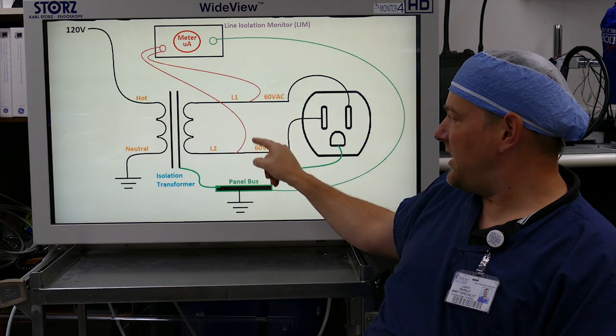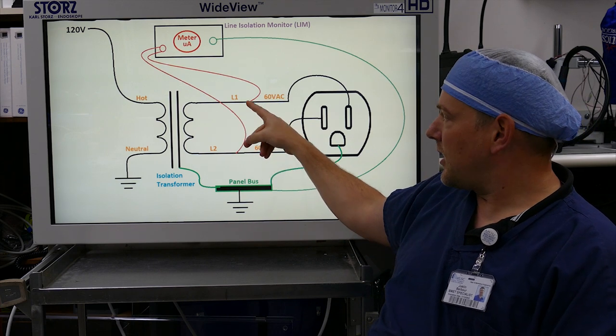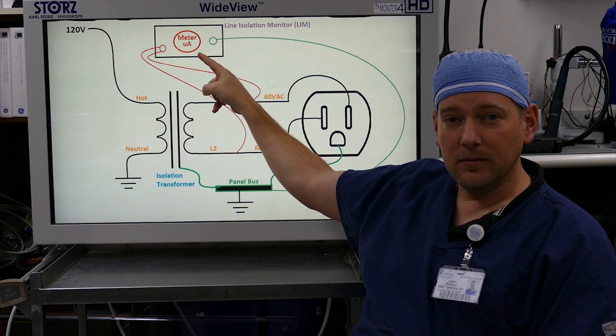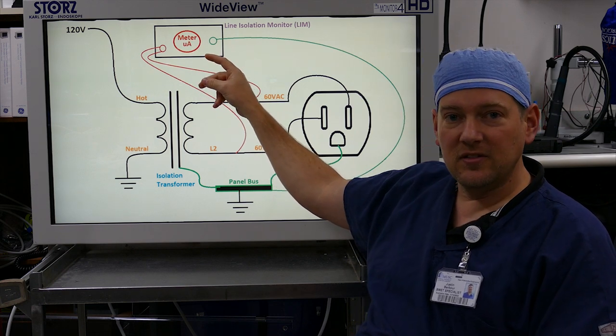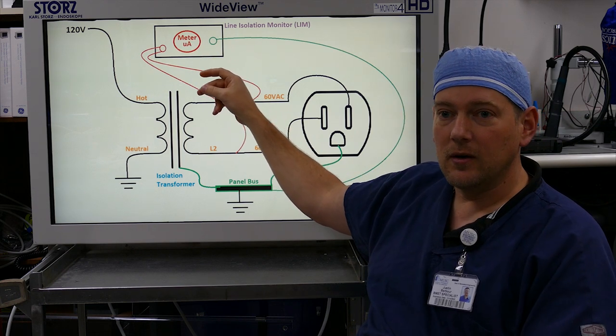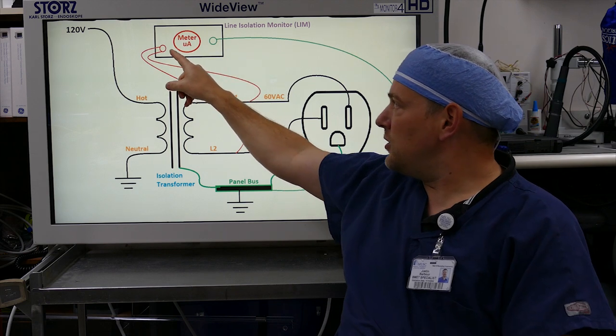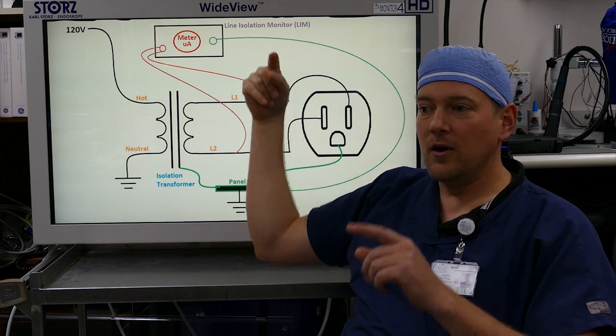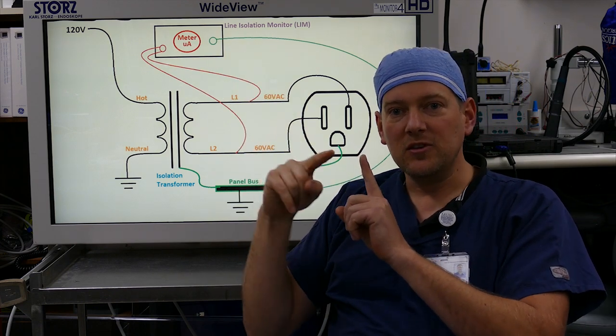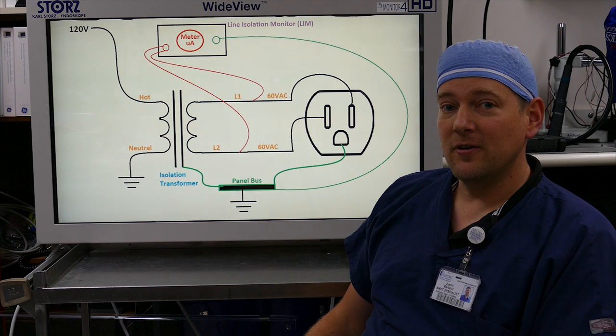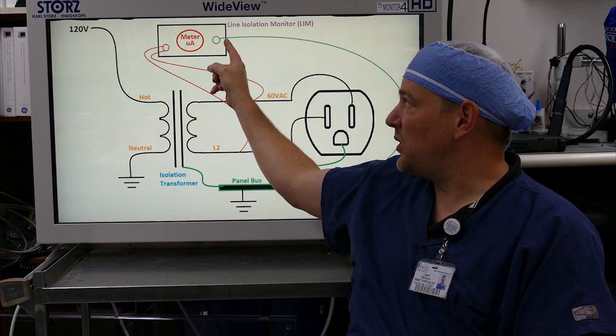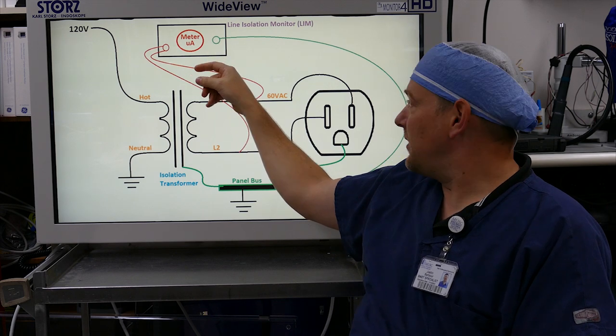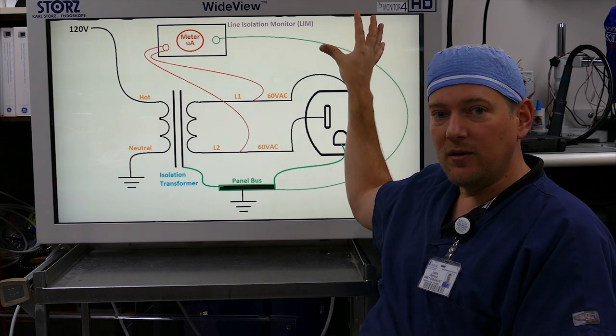So from L1 and L2 coming off the transformer you have wires that go all the way up to your meter and it's basically the same as on a multimeter on microamps or milliamps. You have on one side L1 and L2, and on the other side ground. So between those two is measuring amperage. If a current ever exceeds five milliamps between ground and L1 or L2, then your meter will alarm and it buzzes inside the operating room.